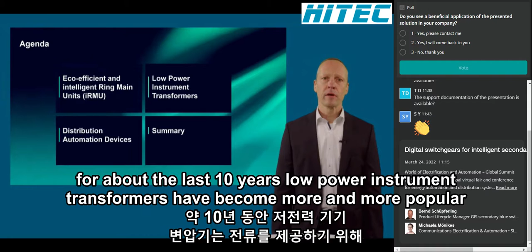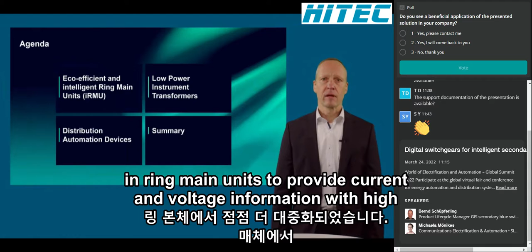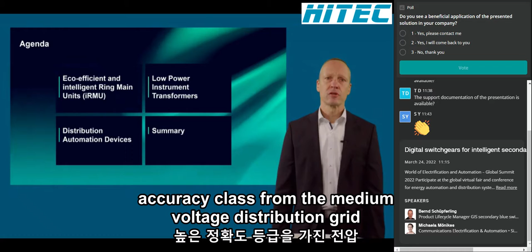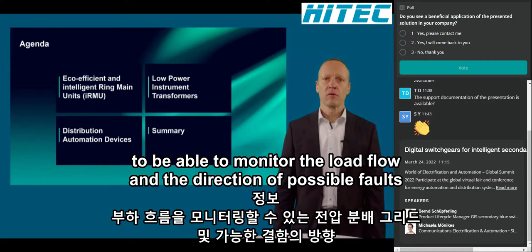For about the last 10 years, low power instrument transformers have become more and more popular in ring main units to provide current and voltage information with high accuracy class from the medium voltage distribution grid to be able to monitor the load flow and the direction of possible faults.